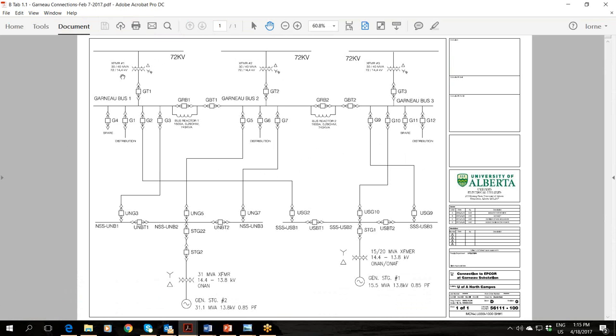So they've got a 3-bus system, 72 kV, and their secondary transformer is 14.4. By the time it gets to us, it's about 14.2, and by the time we get it to our customer base, it's about 13.8. So we call it nominally 13.8. But just in terms of architecture, they have the 3-bus system. We get 2 supplies off of each of these 3 buses.